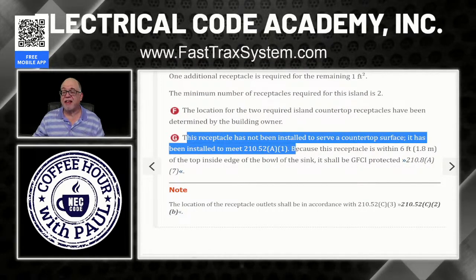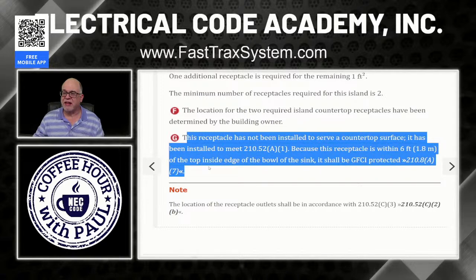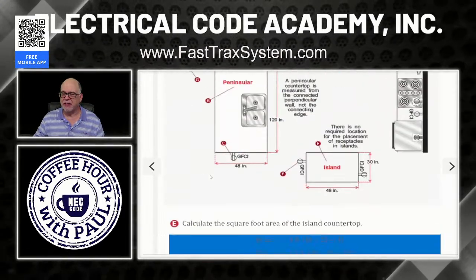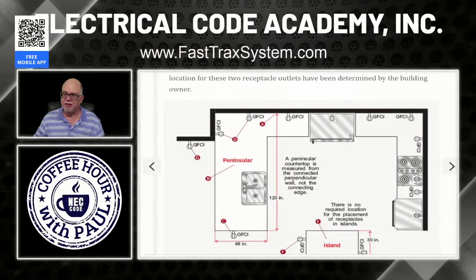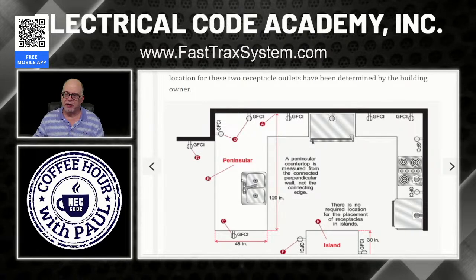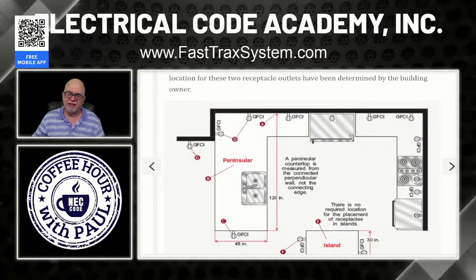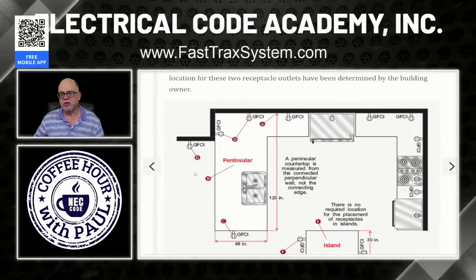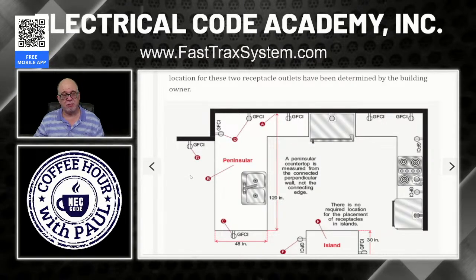But since that receptacle is within 6 feet of the top inside edge of the bowl of the sink, guess what? It may be the living room, but it's required to be GFCI protected. And remember, the measurement is from the top inside edge, straight as if it was a cord plugging in. So across the countertop and then at an angle straight down to the receptacle. If that is within 6 feet, then this receptacle would have to be GFCI protected, even though it's not serving the countertop, it's serving the wall space. So important to remember those things, folks. Really important.